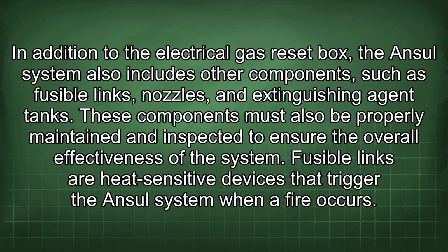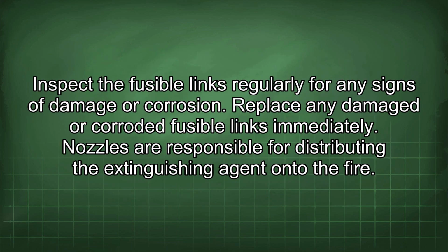In addition to the electrical gas reset box, the Ansul system also includes other components such as fusible links, nozzles, and extinguishing agent tanks. These components must also be properly maintained and inspected to ensure the overall effectiveness of the system. Fusible links are heat-sensitive devices that trigger the Ansul system when a fire occurs. Inspect the fusible links regularly for any signs of damage or corrosion. Replace any damaged or corroded fusible links immediately.